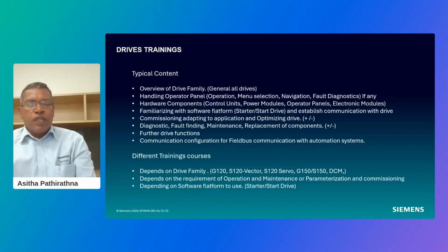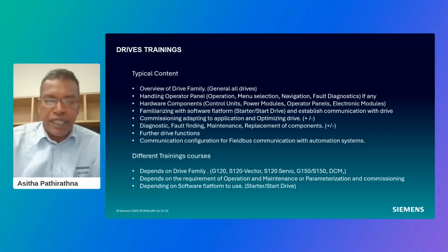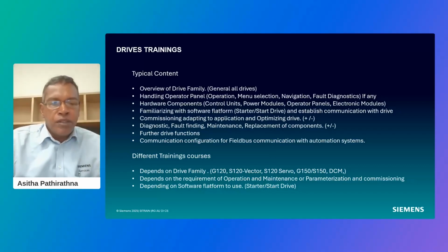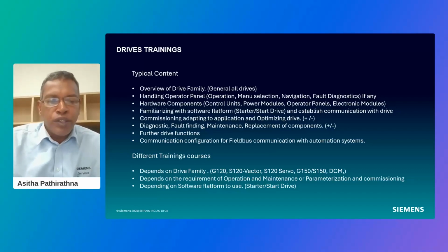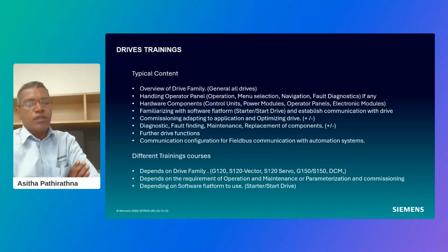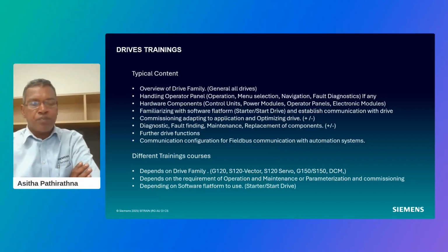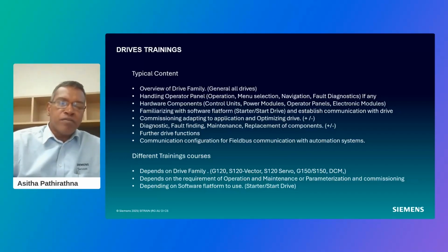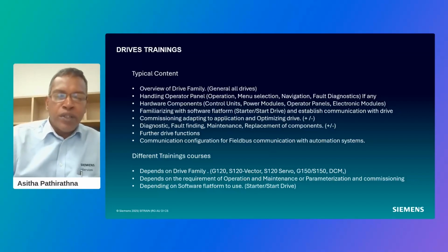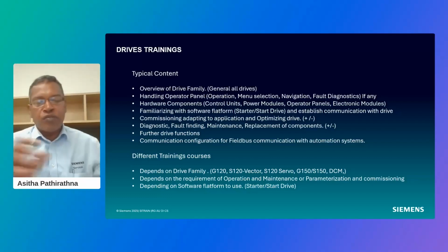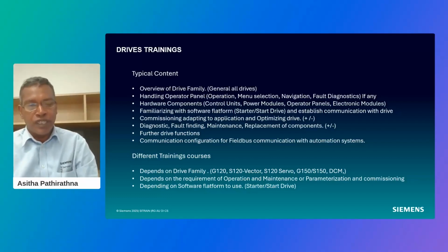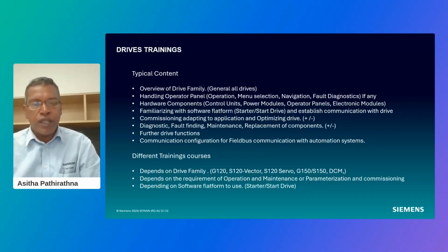So if you want drives training or Siemens drives training, we have an offer. First, you need to know which drive family you want to learn about, whether it's G120 or S120. In the S120 drive, you can also use vector mode or servo mode. Vector mode means driving large power range motors, where load moment of inertia to motor moment of inertia is a big number. In servo drives, load moment of inertia is pretty much equal to motor moment of inertia. So you need to decide which drive family you want to learn about.